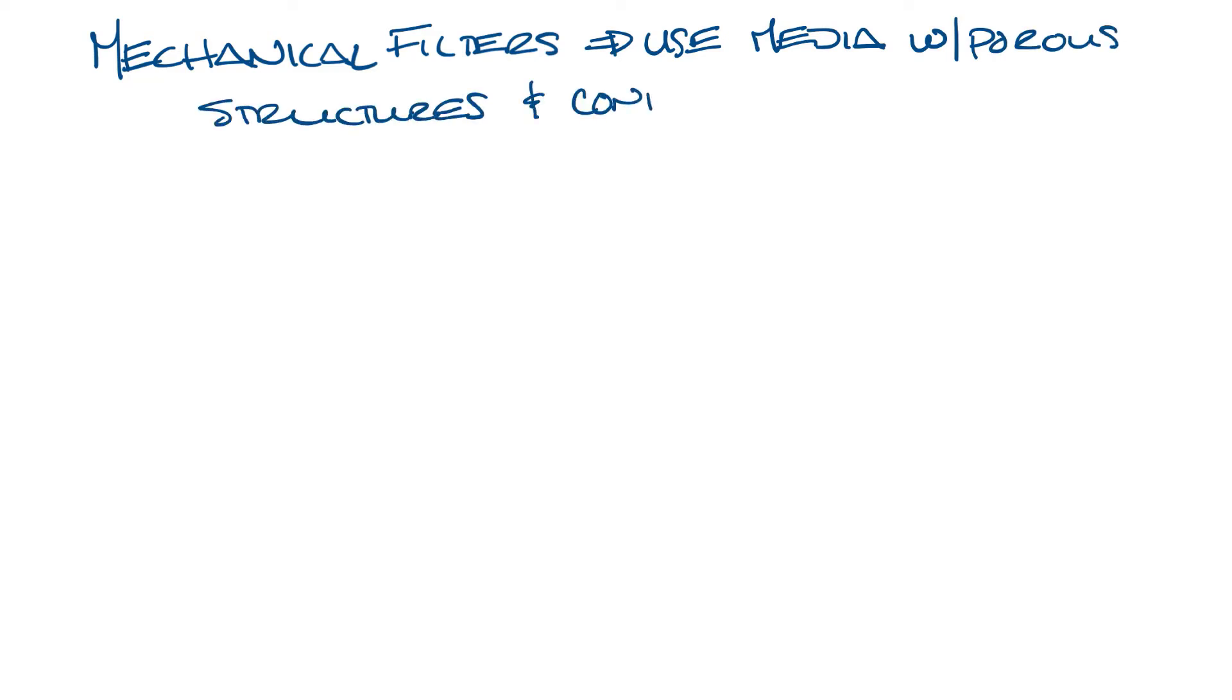There are a lot of different filtration and disinfection technologies available today, but I'm going to stick to just basic mechanical filters for this video and save other technologies for their own videos. Mechanical filters use media with porous structures that contain fibers or a stretched membrane to remove particles from the airstream. Particles in the air essentially attach to the media as the air passes through it.